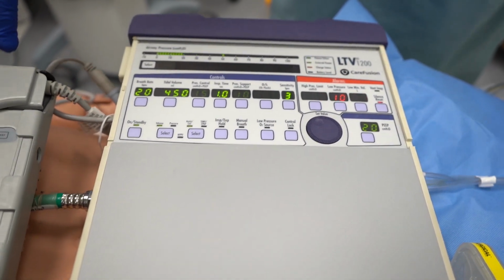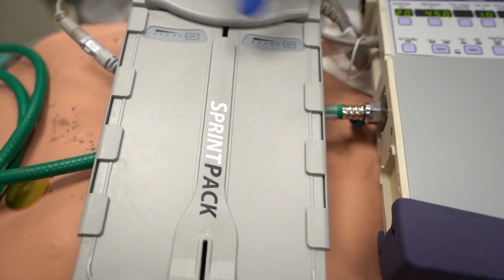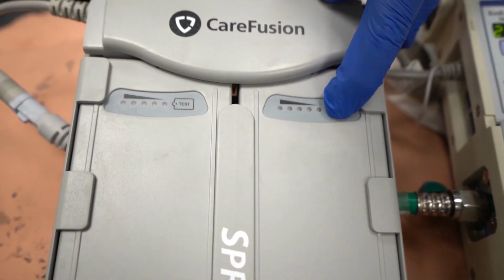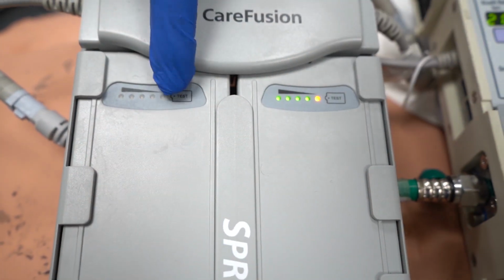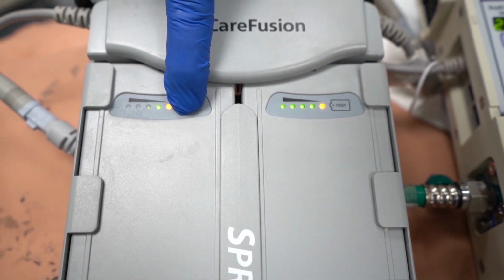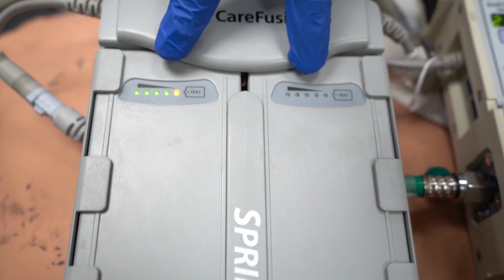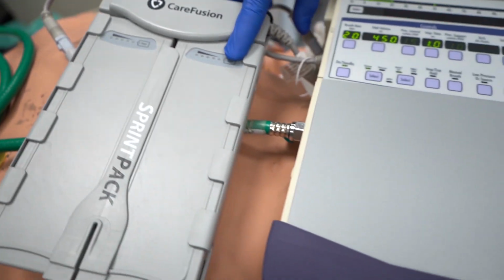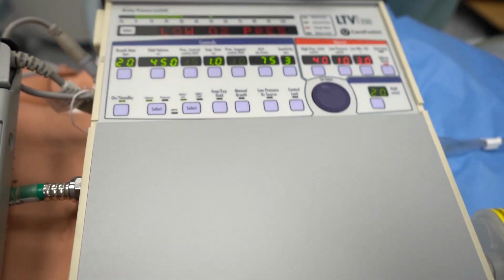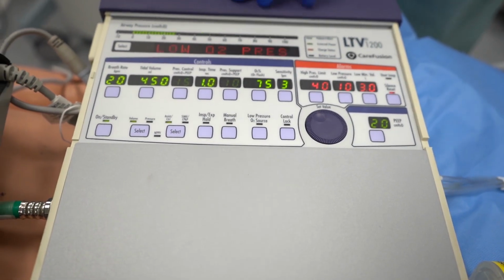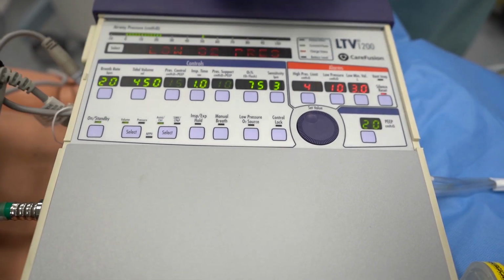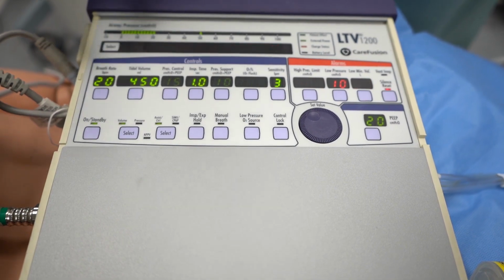On the battery pack itself, there are 2 separate batteries. You can test each one to make sure you have power in each by pressing the test button. So those will light up and tell you how much power you have in those. And then the internal battery of the ventilator itself lasts about 45 minutes without the battery pack. And that's it.